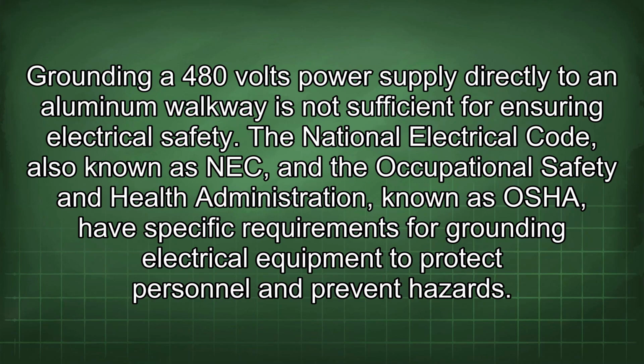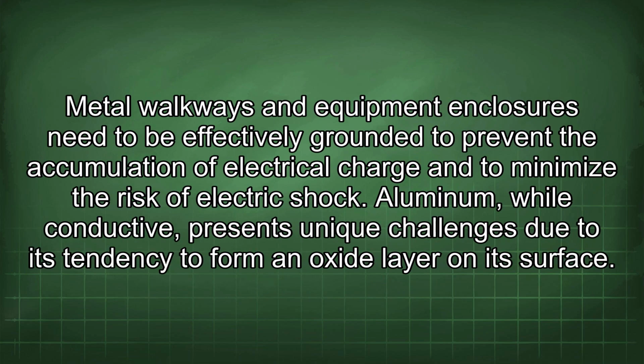Grounding a 480 volts power supply directly to an aluminum walkway is not sufficient for ensuring electrical safety. The National Electrical Code, also known as NEC, and the Occupational Safety and Health Administration, known as OSHA, have specific requirements for grounding electrical equipment to protect personnel and prevent hazards. Metal walkways and equipment enclosures need to be effectively grounded to prevent the accumulation of electrical charge and to minimize the risk of electric shock.